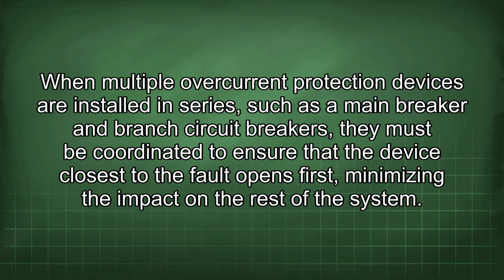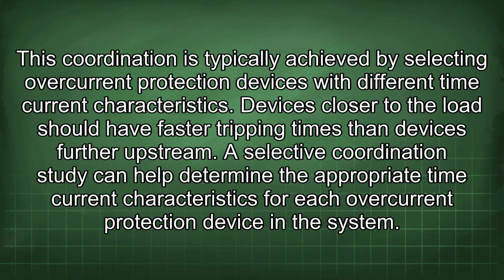When multiple overcurrent protection devices are installed in series, such as a main breaker and branch circuit breakers, they must be coordinated to ensure that the device closest to the fault opens first, minimizing the impact on the rest of the system. This coordination is typically achieved by selecting overcurrent protection devices with different time current characteristics. Devices closer to the load should have faster tripping times than devices further upstream.